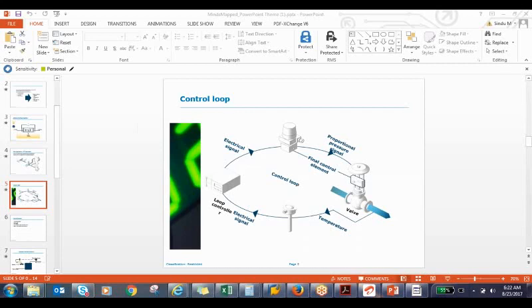You measure the temperature, take it through the RTD cable, and terminate it in a panel. Maybe I will show the practices and pictures in later classes. You will terminate in a panel with the use of something called terminal blocks. Got it? The terminal block will act as a marshalling point where it electrically isolates the signal from the PLC cabinet to the field. The electronics and the field get isolated through marshalling.